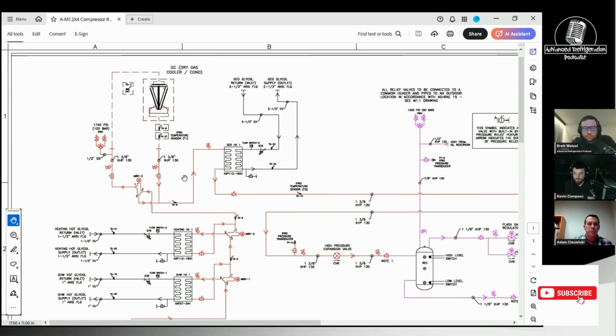It is more complex. But there are certain circumstances where, if we are faced with very light loads and we get some very cold ambients and perhaps even some cross prevailing winds, that even turning the fans completely off, we're still going to see decreasing drop leg temperatures, which can ultimately lead to the rack crashing. You have no choice but to do one of 2 things. You can either split the condenser or the gas cooler, or you can add the 3-way bypass valve. From the perspective of which one's better, in my experience both are successful and both can do a good job. But both can be very finicky in their own ways as far as making sure that they control properly and keep the rack stable.